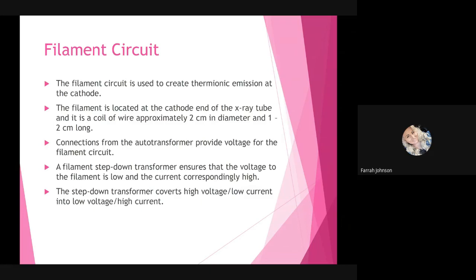Now, connections from the autotransformer are going to provide voltage for the filament circuit. You then have a filament step-down transformer, which ensures that the voltage to the filament is low and the current is correspondingly high. So for your filament, you want a low voltage and a high current, because that current is what's going to cause sufficient thermionic emission, give us the tons of electrons that we need for X-ray production. Now, the step-down transformer is going to convert the high voltage from the high voltage side of the circuit and your low current, and convert them into low voltage and high current, okay, opposite of what was coming in.